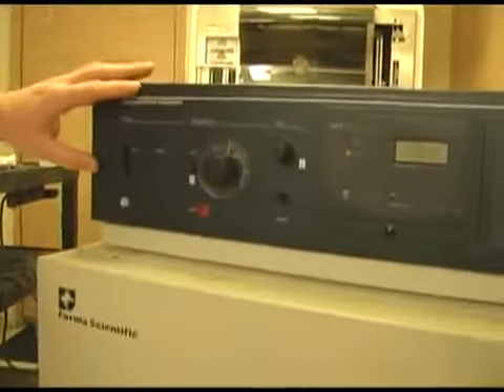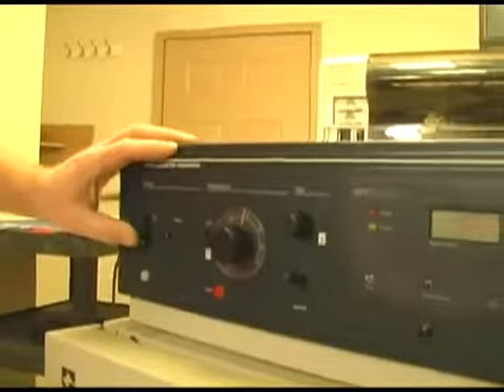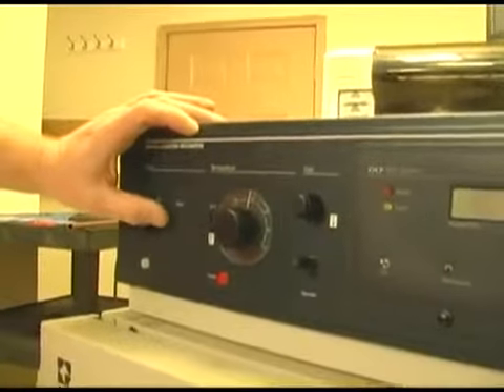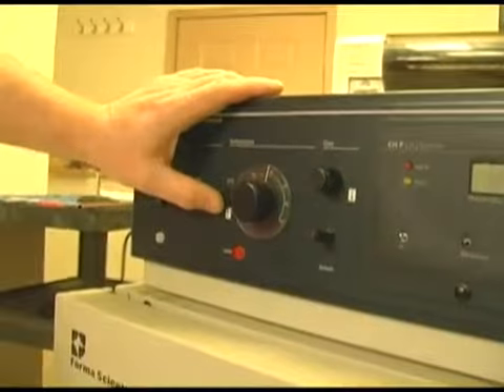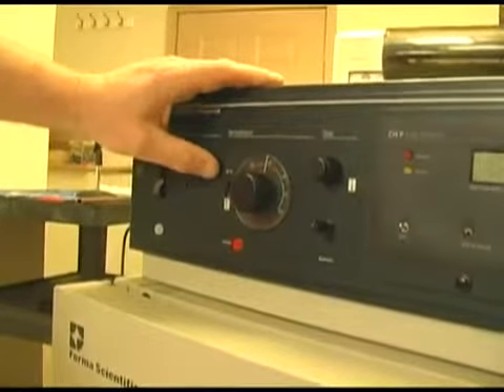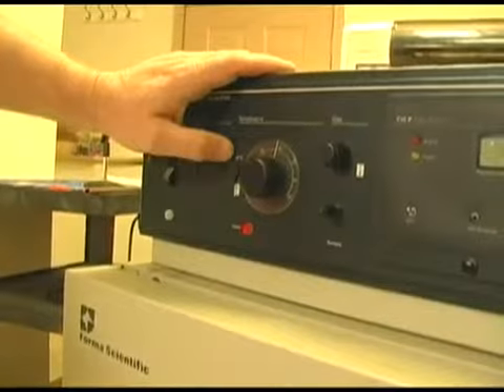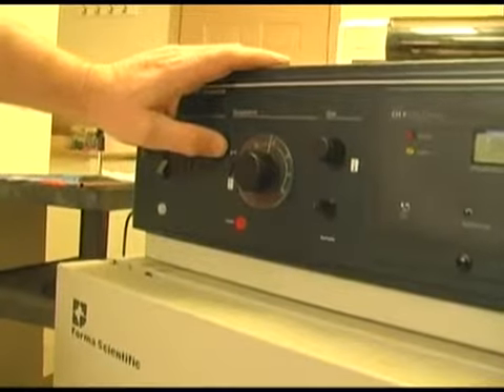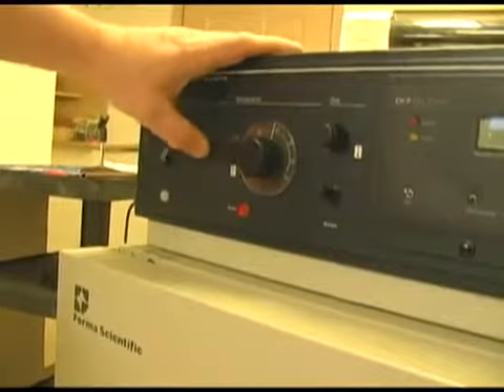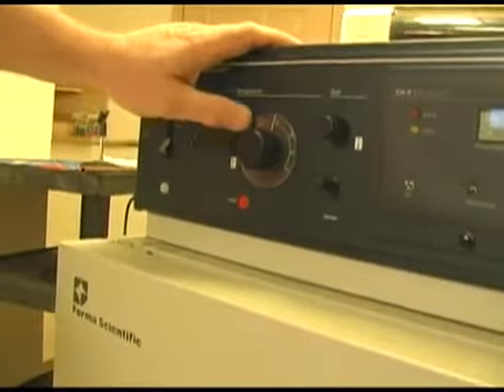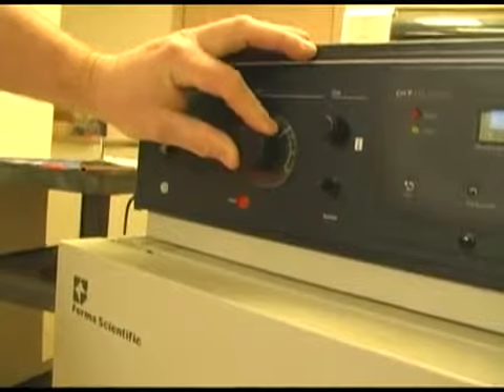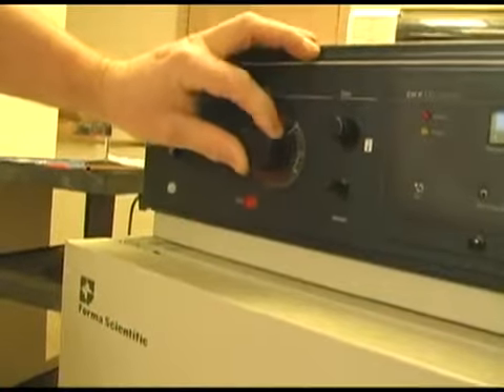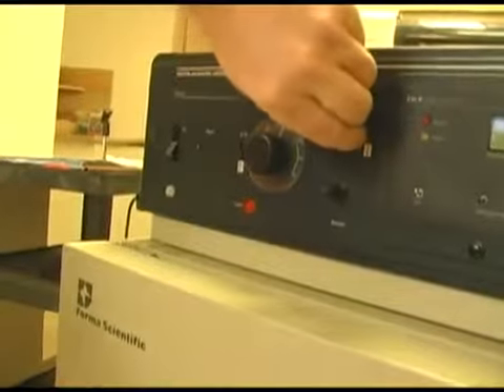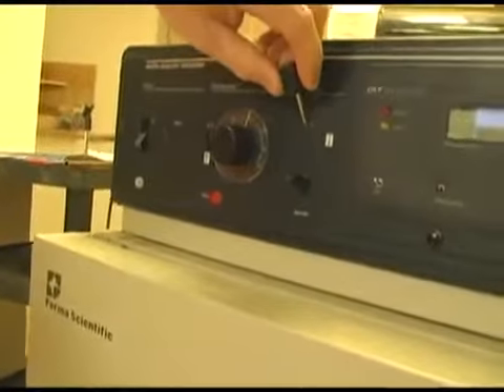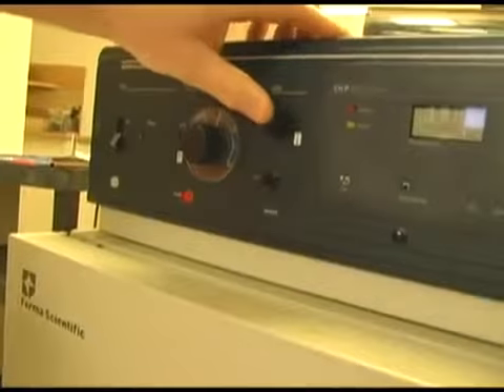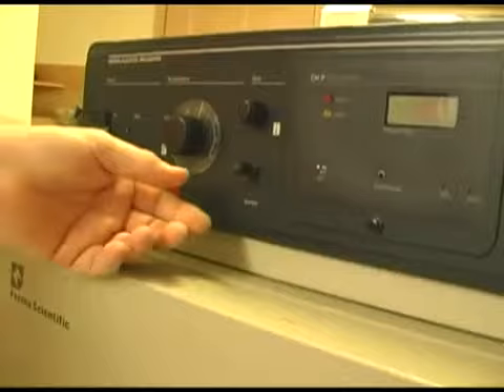On top, left to right, you've got the power on-off switch. You've got a circuit breaker. You have a control here. This particular switch keeps it at 37 at all times. It's a common set point for most people. But if you have something special, you can throw it into the bottom position, and then you use this knob to do your set point, as an example 40 or whatever. Right here, this is simply an adjustment for you. So just a little teeny screwdriver. This allows you to do some calibration and set your set points.